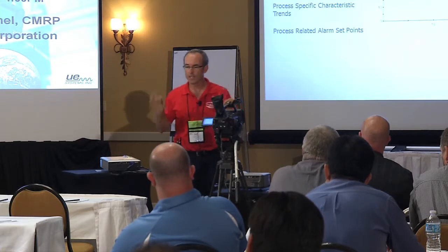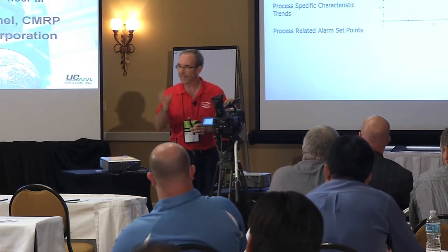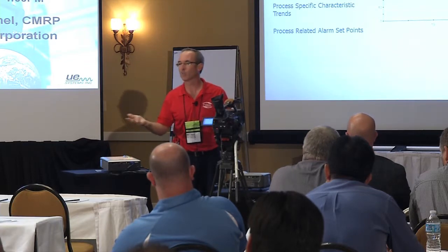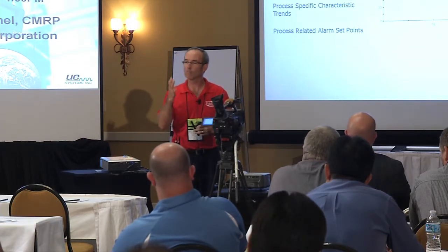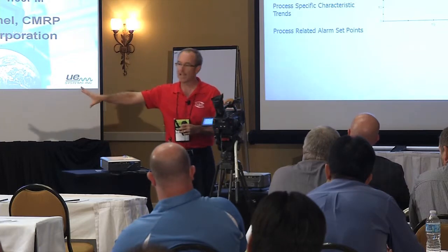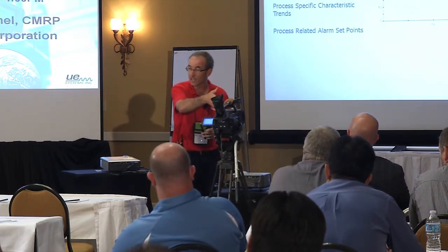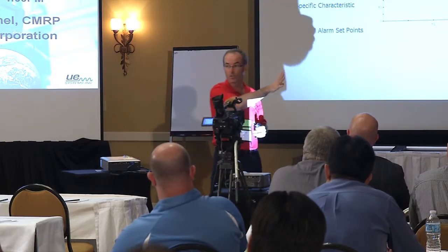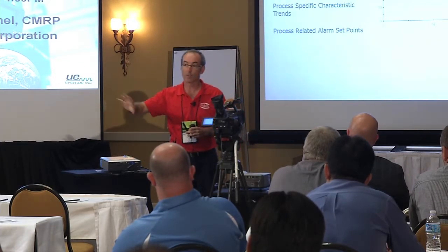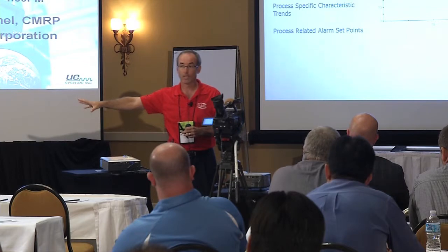We don't look at VFDs so much from the transient, the rise-time side—the transistors are firing in microseconds. We look more at what the VFD provides to the motor. So we like to test line side of the drive, because the drive has quite an effect on the distribution, and we also test load side of the drive, which is what's actually affecting the motor.